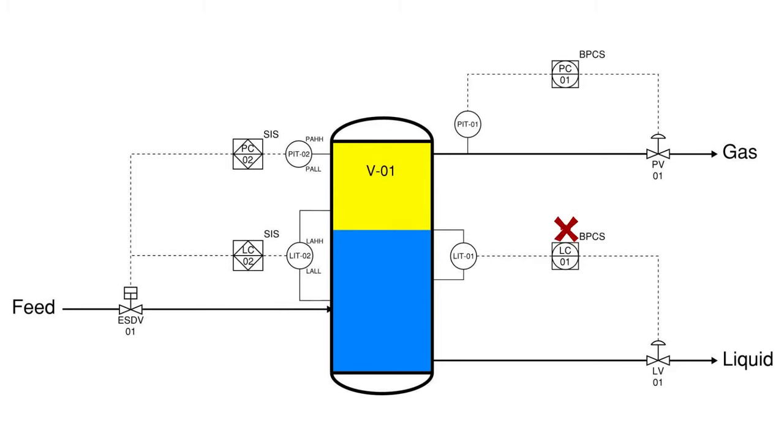If the BPCS controls fail and level in the vessel begins to increase, when the liquid level gets too high and reaches the set point of the level alarm, high-high or LAHH of LIT-2, the controller LC-2 will alarm and send the signal to close ESDV-1.